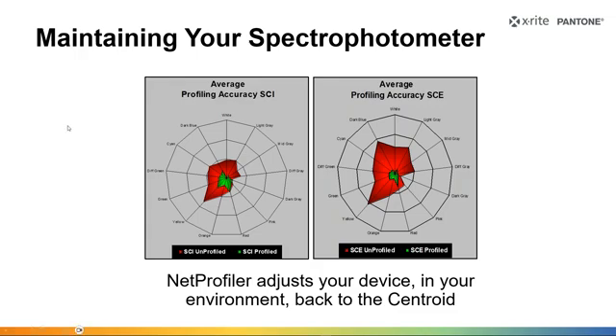The green is after a profile was applied to those instruments. So all the space between the red and the green that you can see, all of this area is error that's been corrected by Net Profiler. You can think of it like this: it's brought these instruments from having this kind of cloud of agreement with the centroid, which would be in the dead center, to that kind. So we've reduced that much error, right?